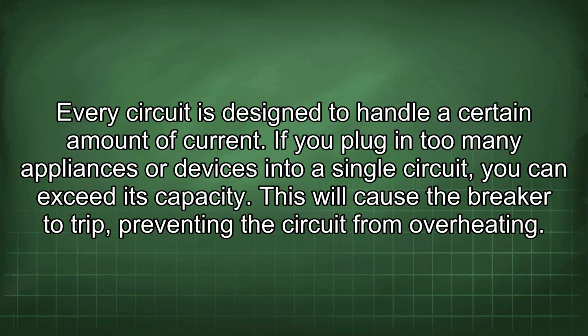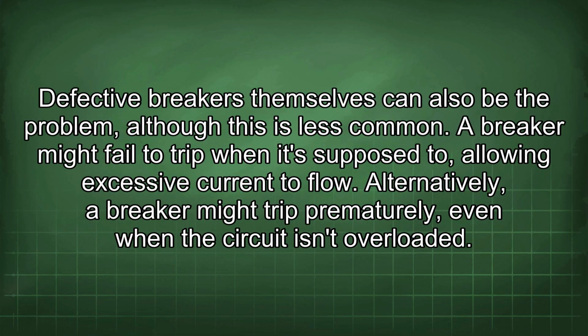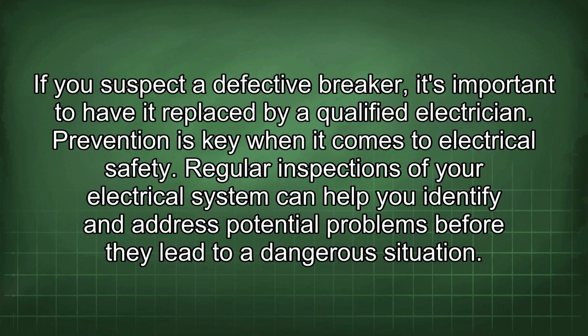Every circuit is designed to handle a certain amount of current. If you plug in too many appliances or devices into a single circuit, you can exceed its capacity. This will cause the breaker to trip, preventing the circuit from overheating. Defective breakers themselves can also be the problem, although this is less common. A breaker might fail to trip when it's supposed to, allowing excessive current to flow. Alternatively, a breaker might trip prematurely even when the circuit isn't overloaded. If you suspect a defective breaker, it's important to have it replaced by a qualified electrician.